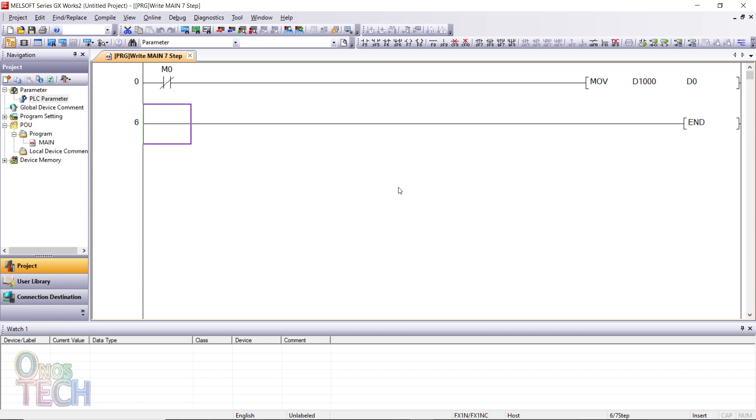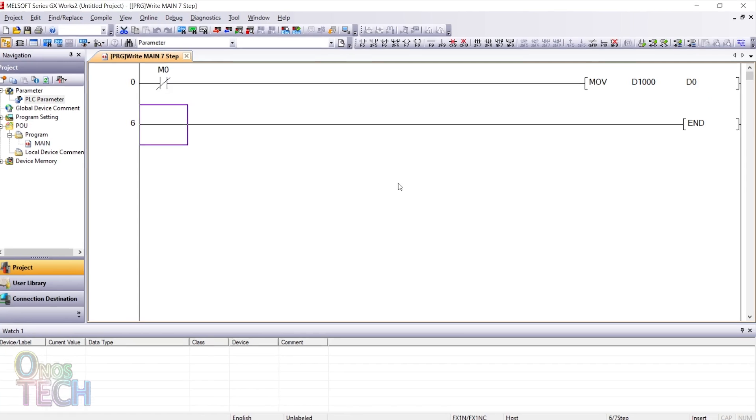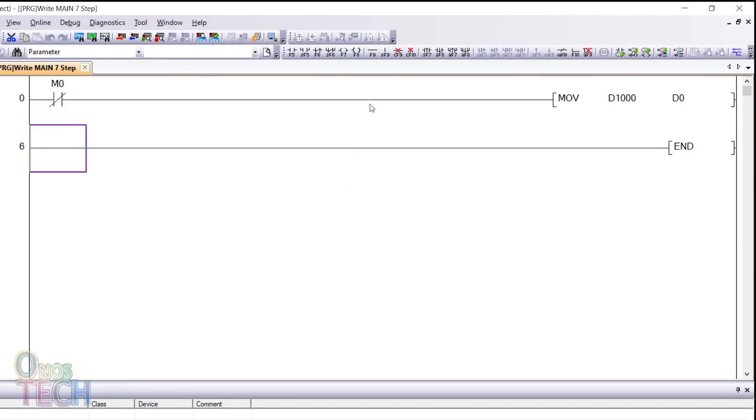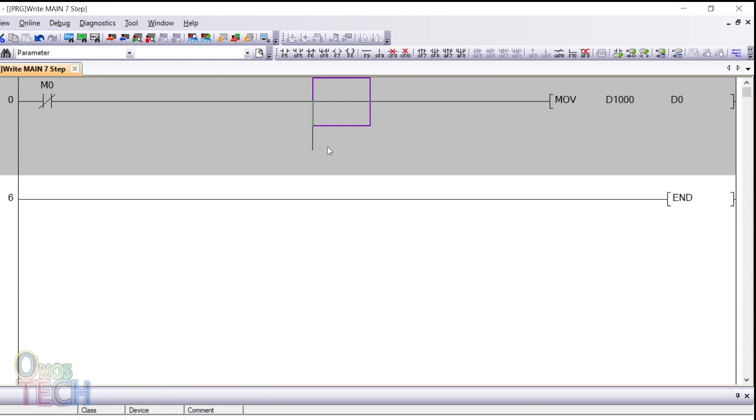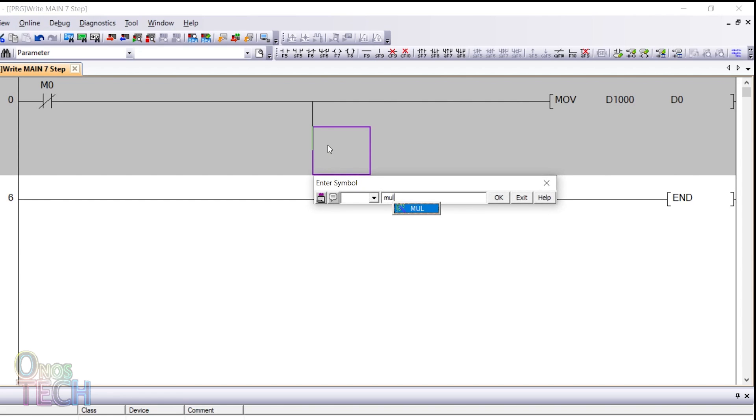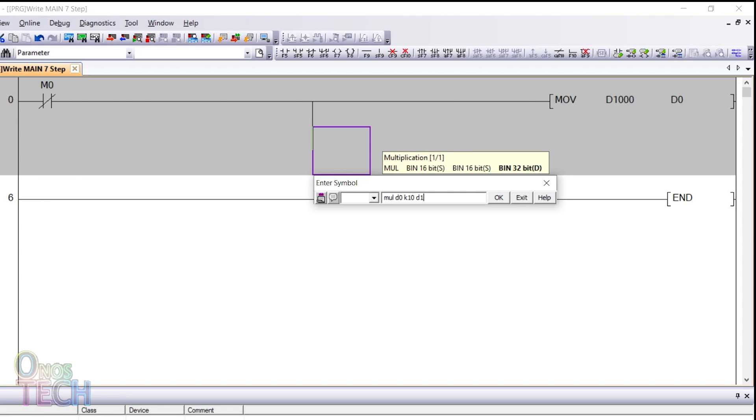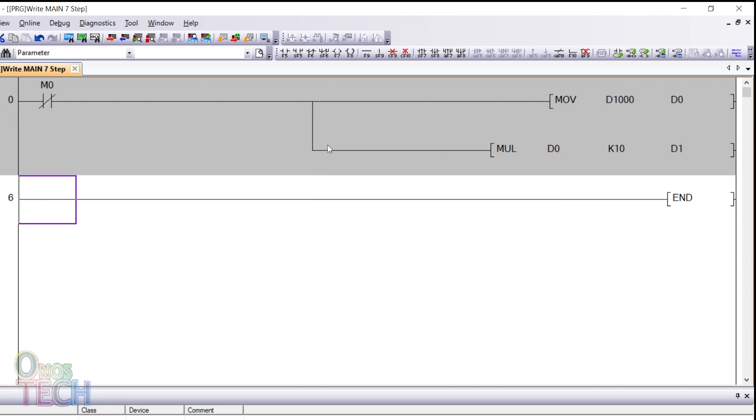Press F2 on your keyboard to stop monitoring the PLC parameters. Add a branch and input MUL D0 K10 D1. This instruction will multiply the analog input value at register D0 with the decimal constant 10 and store the result in register D1.